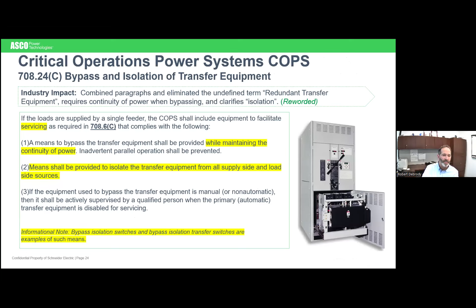This critical operations power system had the same type of wording change. I'm not going to go over it in detail. Here's how the paragraphs were before. As you see, under the redundant transfer equipment, there were no exceptions. It just said that if you had a single transfer switch supplying all of your critical loads, you must have a way to get around it by using a bypass switch. So same wording that we saw previously.